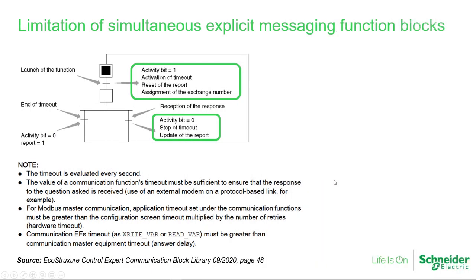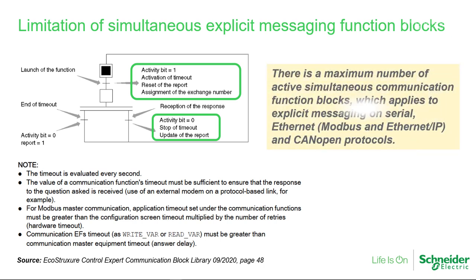One important detail when using explicit messaging is that there is a maximum number of communication function blocks that can be simultaneously active at any given time. This includes the sum of all types of explicit messaging, including Ethernet such as Modbus TCP or Ethernet IP, as well as CANopen or Modbus serial communication. You might need to add logic to control how many function blocks are triggered, and monitor an activity bit to avoid exceeding the communication buffer of the CPU.